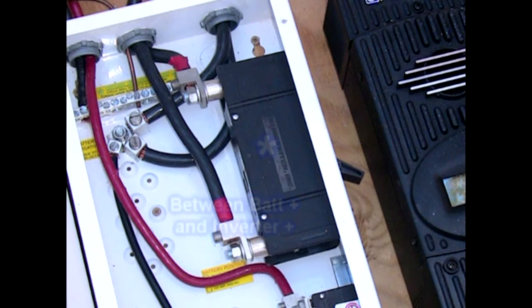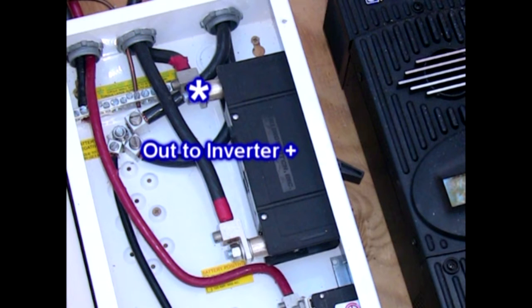It's quite a bit larger, and it's got a big throw lever on the right side of the box. And that is going to be the plus lead again. All the grounds are going to be to that common grounding point. But in this case, our large 2-gauge wire is going about 8 feet. The large one goes into the box from the batteries and goes through that breaker. That hot lead comes out the other side of the breaker, and then is fed out the strain relief in the top of the box and goes out through our conduit pipe under the house and into our inverter.